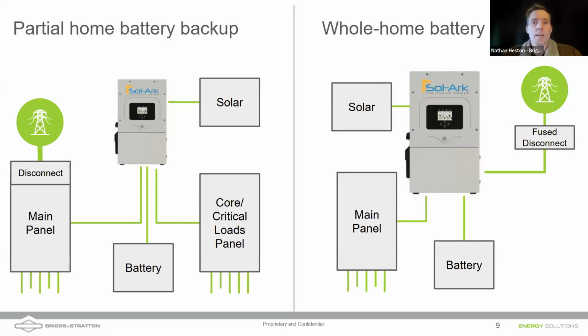And that's the legacy Sol-Ark has, coming out with this inverter in 2018, 2019, hitting the market and backing up whole houses with that 200 amps of pass through. So historically, what you see on the left is what you would have with a solar and battery system. Lead acid batteries were not really capable of delivering that power output for the whole home unless you had a very large bank. Now with lithium batteries, you're looking at double, triple the number of cycles, so triple the lifetime. You're looking at greater power density, so a smaller battery pack can output enough power to actually back up your whole home. That's what you were seeing with our 20 kilowatt hour stack there.